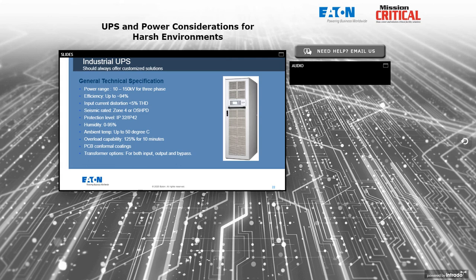Overload capability at least 125% for a few minutes, maybe higher. Keep in mind that if we see an overload that's greater than 125 to 150% for more than a few seconds, that means there's a problem on the output. Not the kind of thing where you want the UPS to sit there and grind away into an overload for 3 days. You want that problem to be solved by clearing a downstream fault or transferring to bypass so that we don't run the risk of overheating or causing the UPS to fail. But it's typical to see overload capabilities from 125 to 150% for some period of time to handle transient overload.